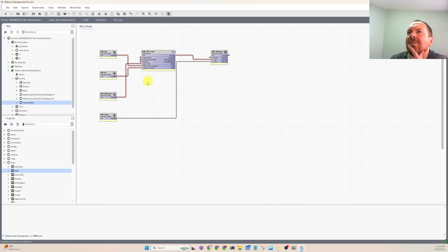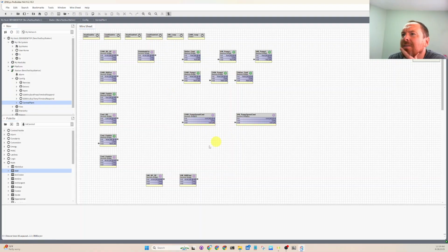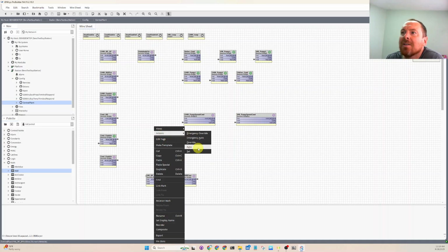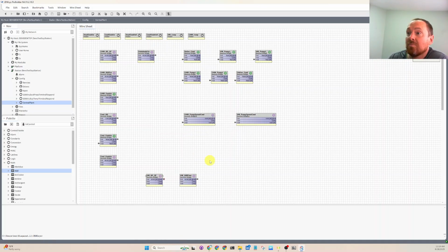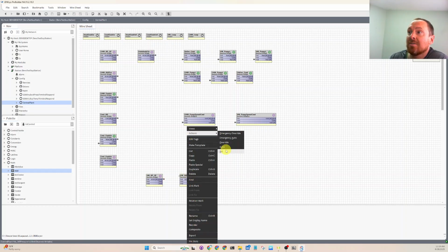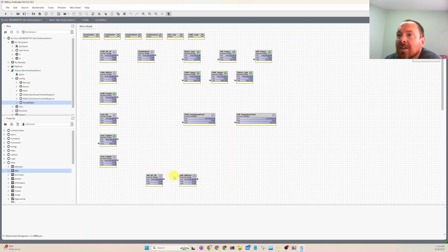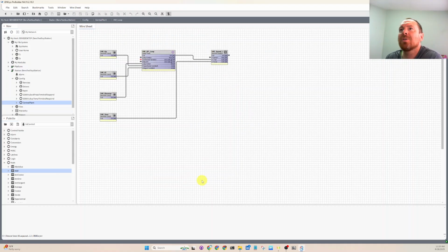So it looked like it is that right. So the control variable is 10 and the set point is 20. So if I just go back up here, yeah, 10 and 20. Oh wait, so right now we need our set point to be 10 and the differential pressure sensor to be 20. Okay, so right now we should be under set point. We should have a speed command. The PID should start ramping up.